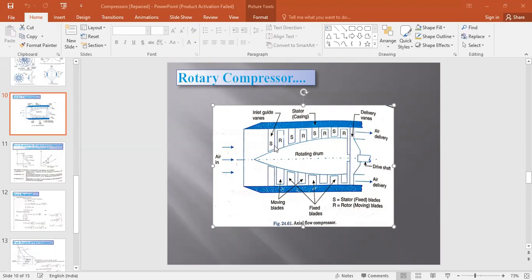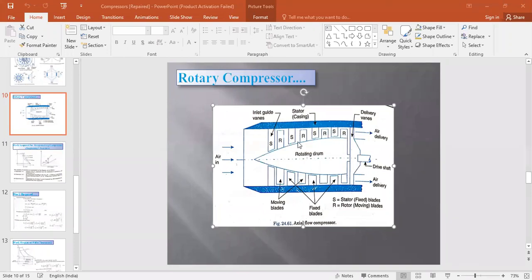One stage is the set of stator and rotor. The second set of stator and rotor is the second stage, and the third set is the third stage. To achieve a high pressure ratio, the number of stages has to be increased — up to four or five stages. The pressure ratio at delivery can be 4.5 to 1, and to achieve 14 to 1 we need at least 15 stages.